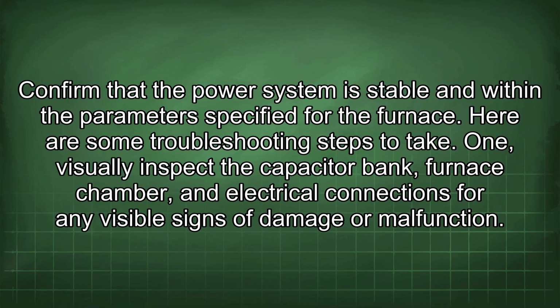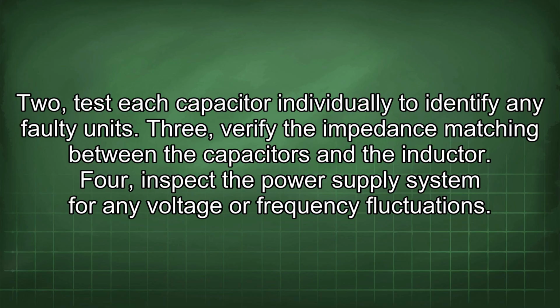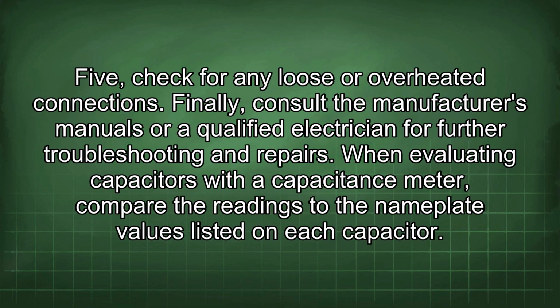Here are some troubleshooting steps to take. 1. Visually inspect the capacitor bank, furnace chamber, and electrical connections for any visible signs of damage or malfunction. 2. Test each capacitor individually to identify any faulty units. 3. Verify the impedance matching between the capacitors and the inductor. 4. Inspect the power supply system for any voltage or frequency fluctuations. 5. Check for any loose or overheated connections. Finally, consult the manufacturer's manuals or a qualified electrician for further troubleshooting and repairs.